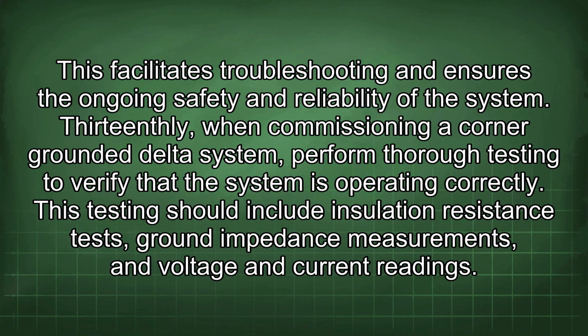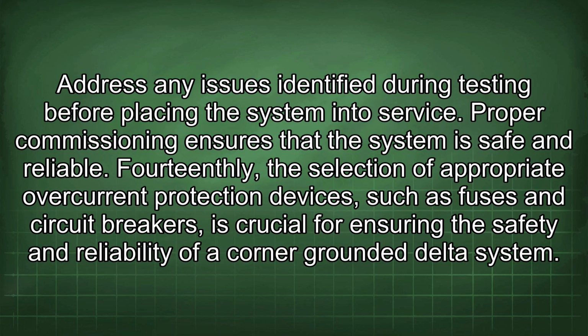13thly, when commissioning a corner-grounded delta system, perform thorough testing to verify that the system is operating correctly. This testing should include insulation resistance tests, ground impedance measurements, and voltage and current readings. Address any issues identified during testing before placing the system into service. Proper commissioning ensures that the system is safe and reliable.